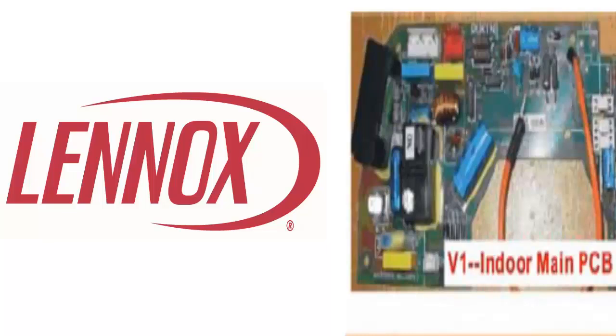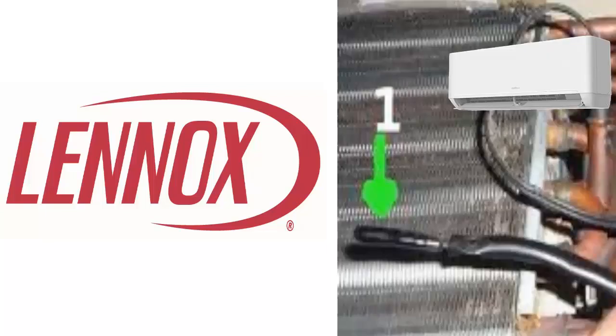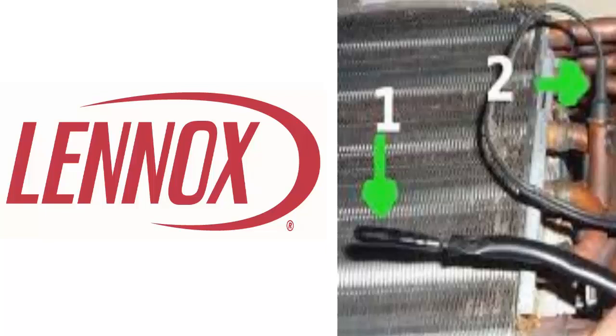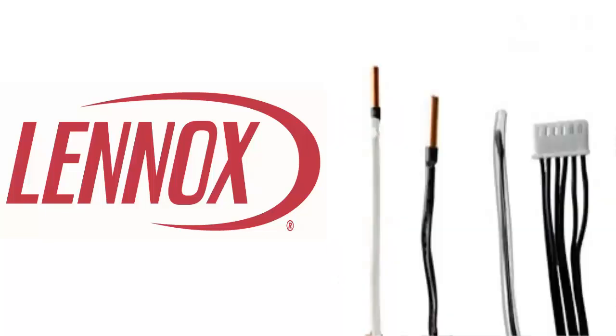To begin with, it's important to note that the electronic controller of the unit typically detects problems in temperature sensors when a short circuit or an open circuit in the sensor is identified. However, these are not always the real causes of the problem. For example, a code indicating an open circuit may simply be due to a loose sensor connection. Therefore, as we will see below, the problem can often be resolved with simple techniques since the components of the unit are usually in perfect condition.